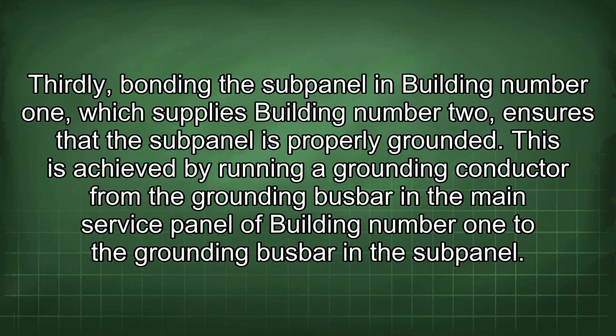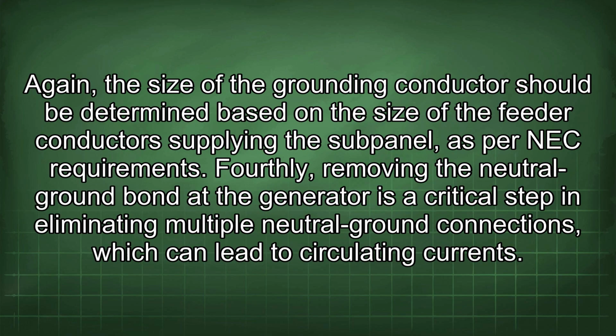Thirdly, bonding the subpanel in building number 1, which supplies building number 2, ensures that the subpanel is properly grounded. This is achieved by running a grounding conductor from the grounding busbar in the main service panel of building number 1 to the grounding busbar in the subpanel. Again, the size of the grounding conductor should be determined based on the size of the feeder conductors supplying the subpanel, as per NEC requirements.